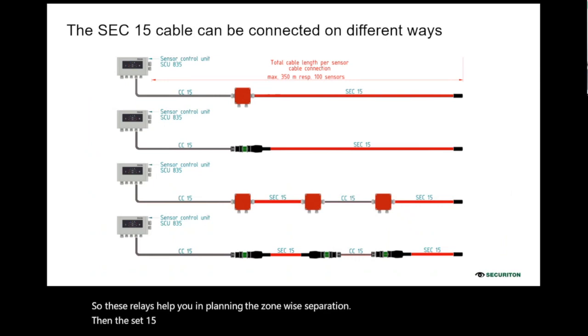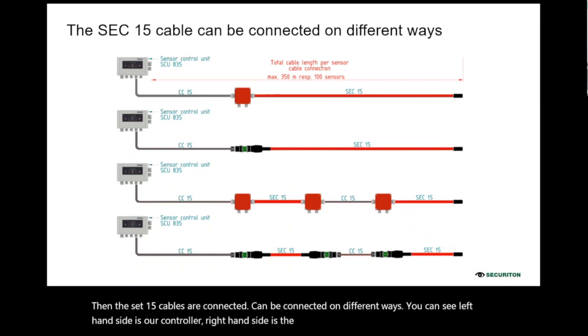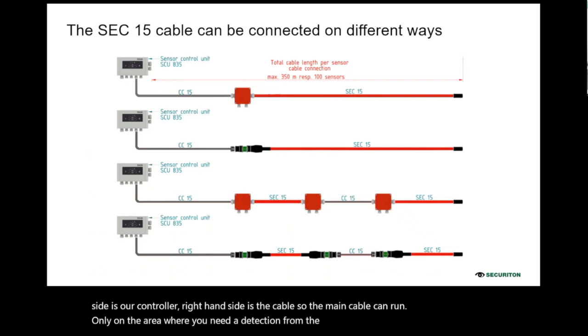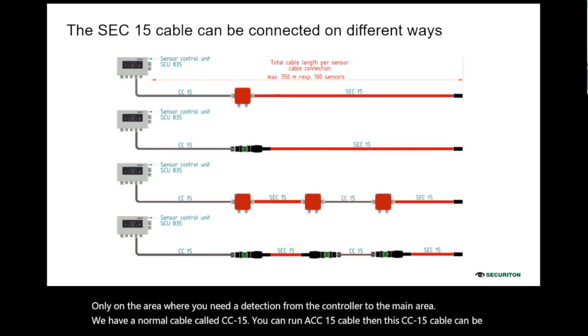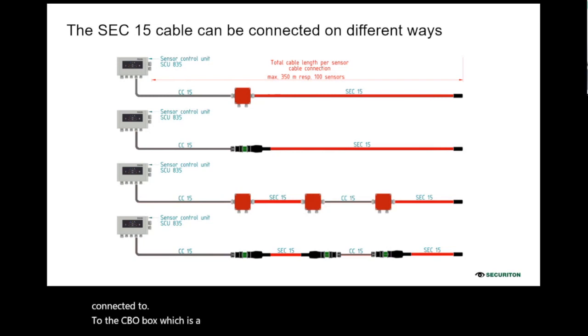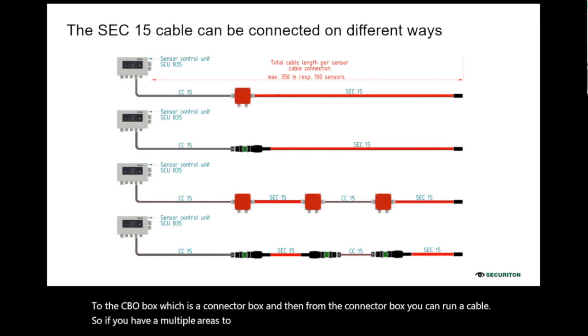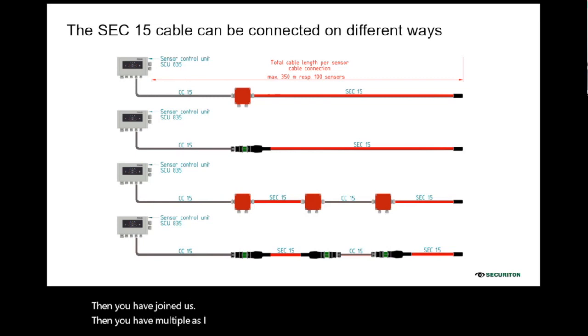SEC15 cables can be connected in different ways. You can see the left-hand side is our controller, the right-hand side is the cable. The main cable runs only in the area where you need detection. From the controller to the main area, we have a normal cable called CC15. This CC15 cable can be connected to the CBO box, which is a connector box, and from the connector box you can run the sensor cable. If you have multiple areas to monitor, you put multiple connectors in between and then run the cable only in the detection area. Then you have jointers. As I said, you can have multiple controllers, multiple connection boxes in between, and multiple jointers as well.